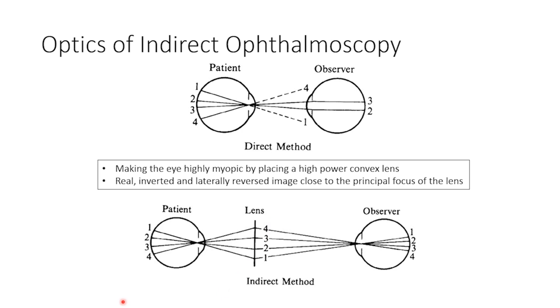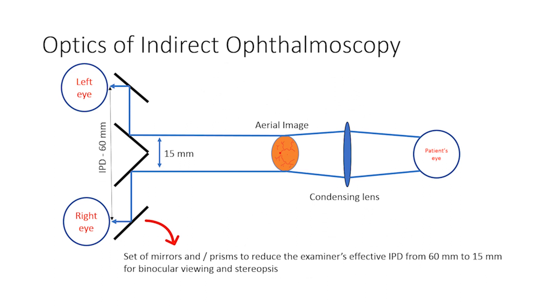In the direct method, the rays of light emerging from the periphery are not reaching the examiner's eye. But in the indirect method, because of the condensing lens, the peripheral rays of light are also brought to focus at the plane of the aerial image, thus enabling peripheral viewing of the retina. In a binocular indirect ophthalmoscope, the optics convert the examiner's interpupillary distance of approximately 60 mm to 15 mm using a set of mirrors, and this allows for stereopsis as both eyes simultaneously perceive a slightly different area of the aerial image.